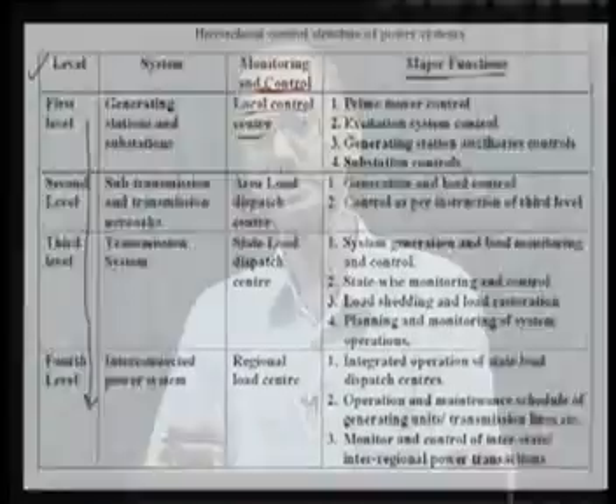For example, say there is some problem in the BFP, the boiler feed pump of a thermal power station. That is a local problem. It has nothing to do with the central dispatch center. That problem must be sorted out within the local control structure itself. The various problems in that control must be taken care of by the local operators, and that is your local control center.